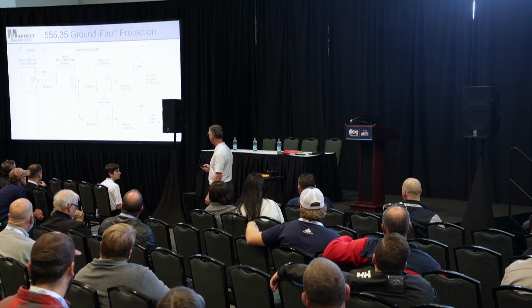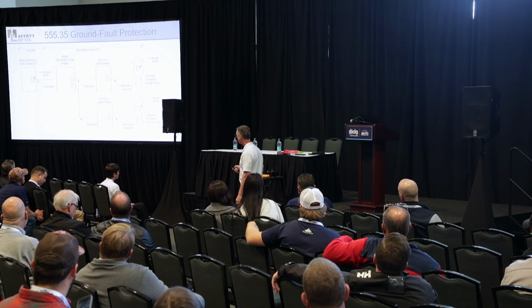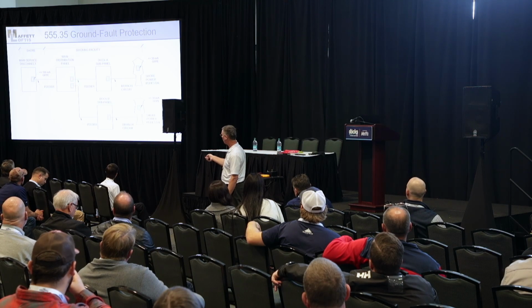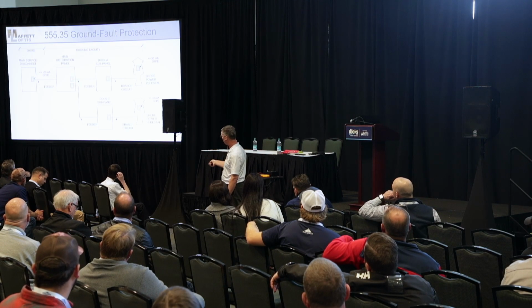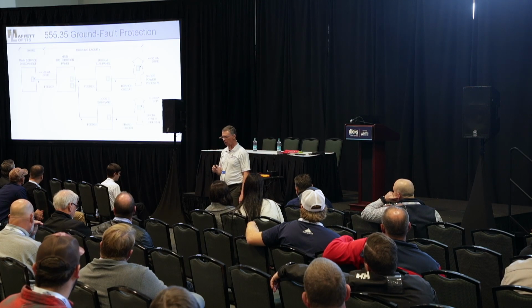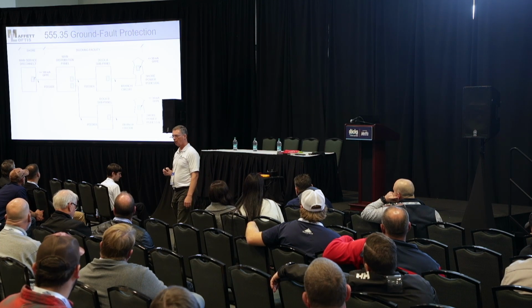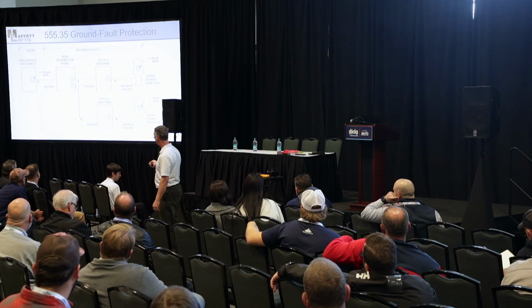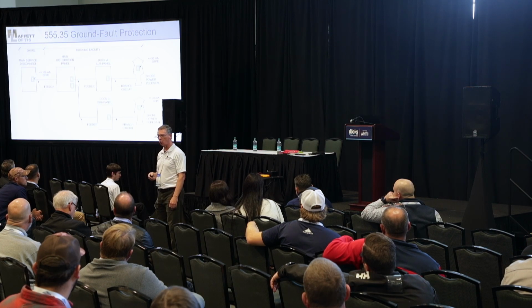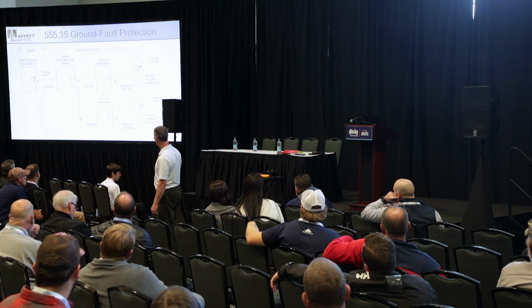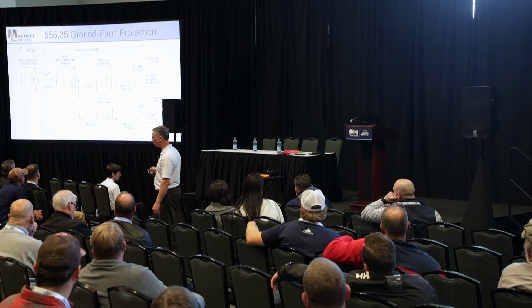And what I mean by that is this. Let me just go through this real quick. At minimum, you'd have to have 100 milliamp up on the shore protecting that feeder, which protects all the other wiring. But at the boat, we have to have 30 milliamp. So we want those two devices, or other GFP devices, to be coordinated so that if a bad boat gets plugged in here, it only trips that one boat, it does not trip up there.